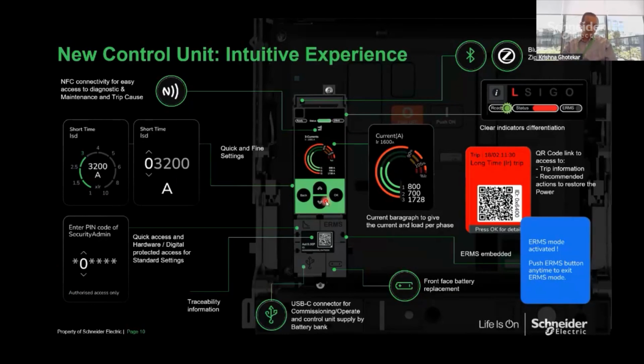Now again, one more common thing, as you know, in the Gulf, for most of the panel FAT, we have to do a secondary injection of a circuit breaker. And one of the key inputs from the partners was about the cable, which today we use for secondary injection to connect to the trip unit. Sometimes, over a period of time, after you do a couple of projects, the pin can get broken because you have to use it for multiple breakers in a single project. On top of that, you need to connect it to a test kit, a hardware module, and that hardware module is connected to a laptop.